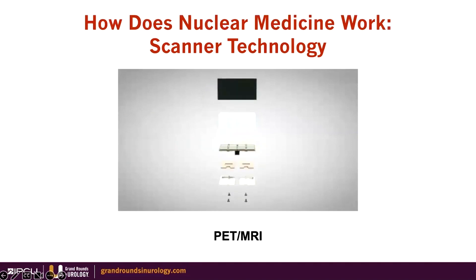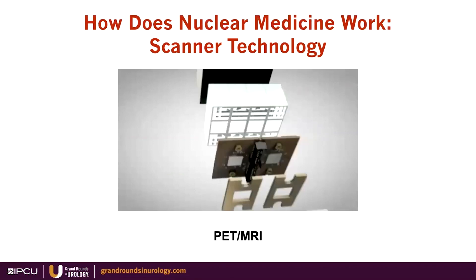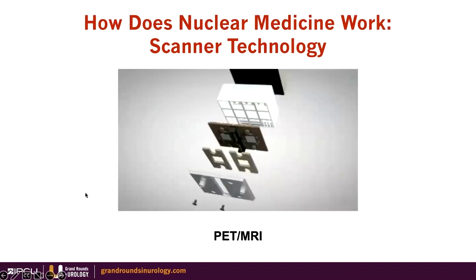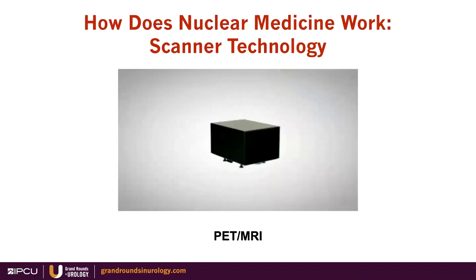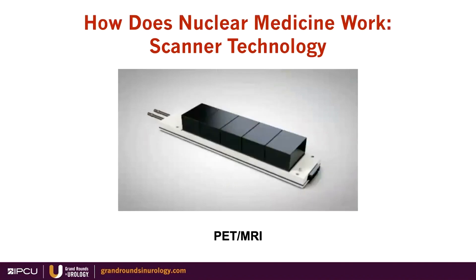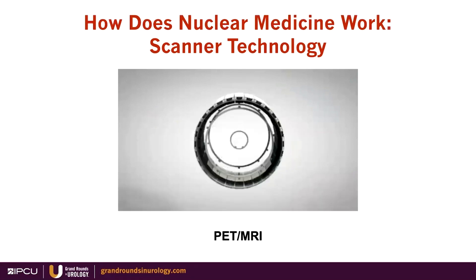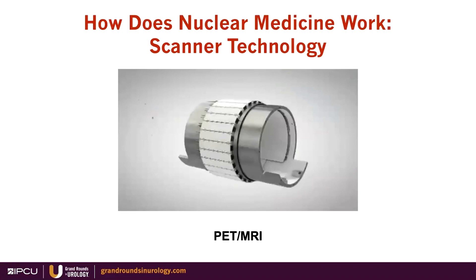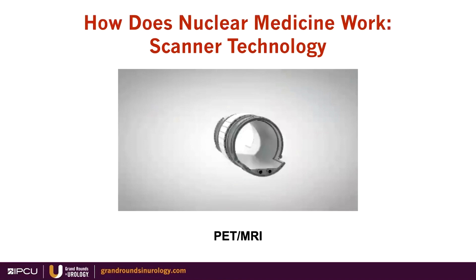What about PET-MRI? PET-MRI is truly simultaneous for most acquisitions, and for that it required a lot more investment. It required going from photomultiplier tubes to silicon photomultipliers — SiPMs — that transform the optical signal directly into an electrical signal sent to a computer. Having these electronics inside a magnet, and having a magnet next to an electronic system, is not easy to accomplish. It took quite a bit of effort, but there are now at least three vendors who produce simultaneous PET-MRIs for human use.